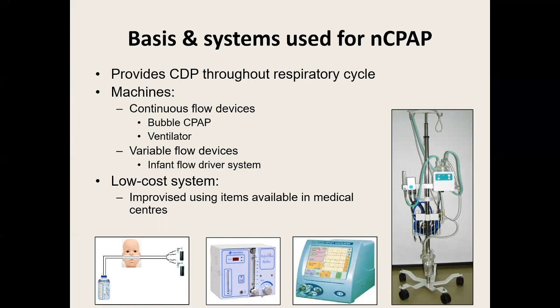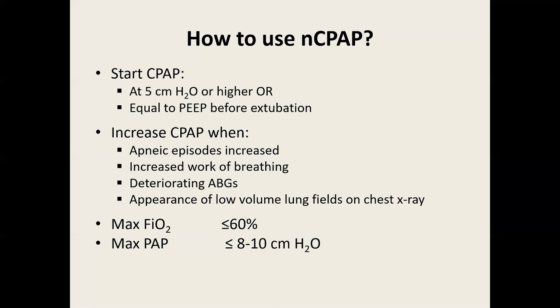The CPAP is generally started at a pressure of 5 centimeters of water with FiO2 of 40 or 50%, or it can also be started at a PEEP equal to the PEEP of the ventilator after extubation. If respiratory distress does not improve with this or worsens further, or oxygenation is impaired, pressure is increased in steps of 1 to 2 centimeters of water to reach a maximum of 8 to 10 centimeters of water. If oxygenation is still compromised, FiO2 is then increased in steps of 5%. While starting CPAP, it is important to resist the temptation of raising FiO2 before pressures for control of hypoxemia.